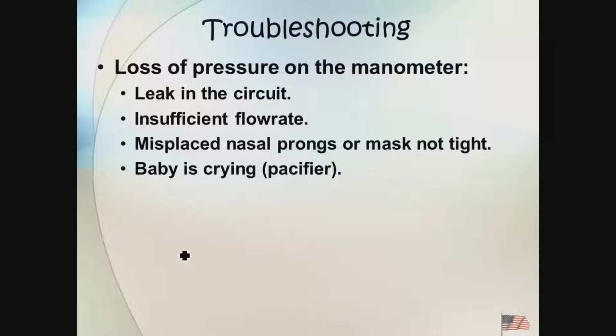All right. Two conditions. Big star, exclamation point. Two conditions. One, your pressure in the circuitry is less than you would anticipate it's supposed to be. I'm supposed to be on 5 of CPAP, I'm only reading 3. They're oscillating around that 3 instead of oscillating around 5. If I don't have enough pressure, the most logical thing is I've got a leak, so make sure everything's tight. The other answer, and this is the answer more often than not, is turn up the flow. The flow is insufficient. If you don't have enough flow going to that reservoir bag, you're not going to have enough flow to keep the pressure within the circuitry high enough to keep my CPAP where I want.